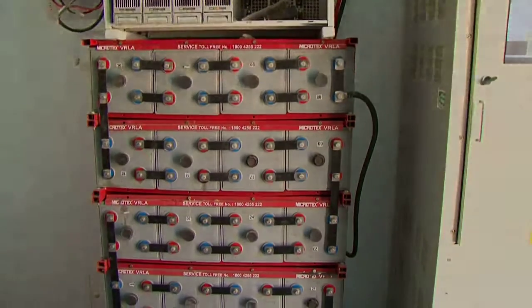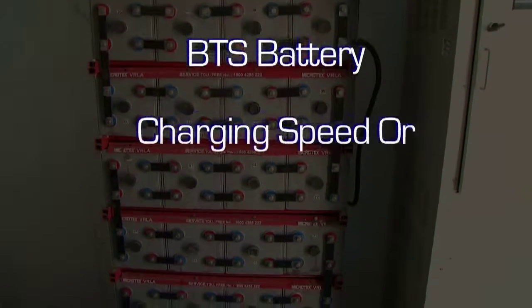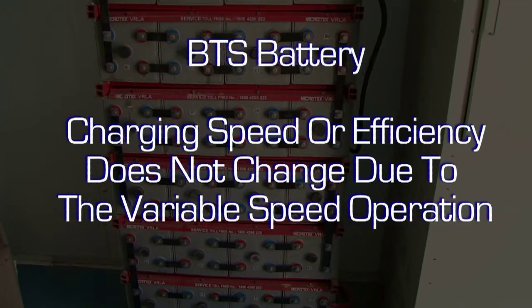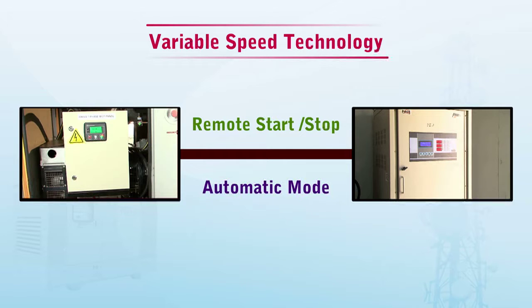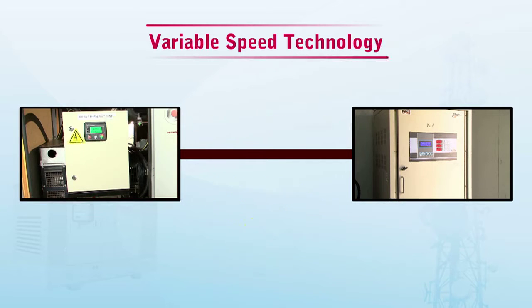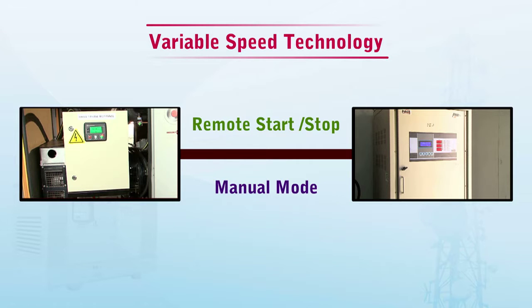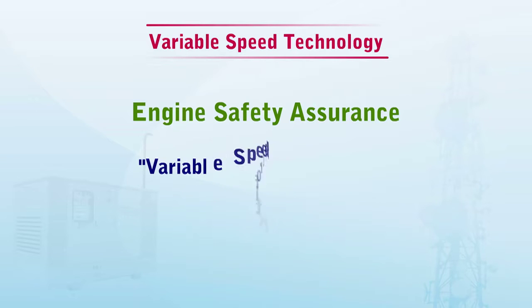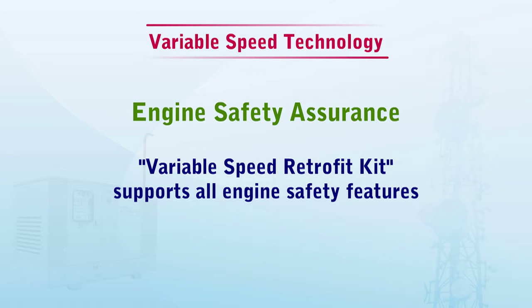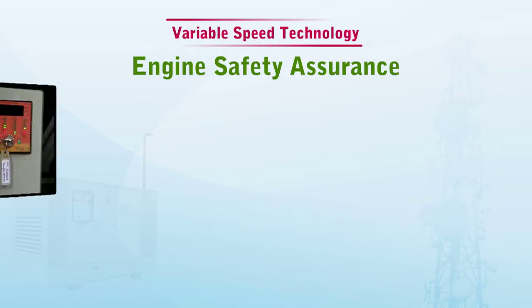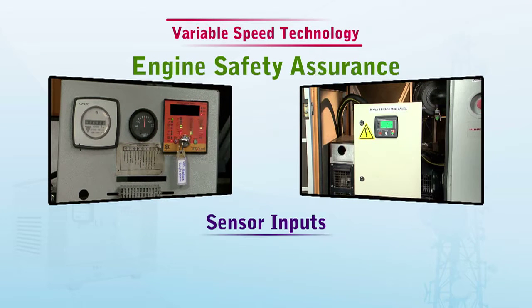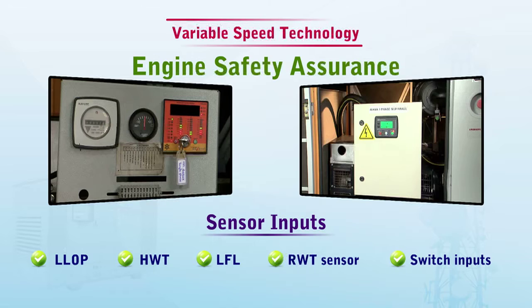One important point to remember is that the BTS battery charging speed and efficiency does not change due to the variable speed operation. The variable speed technology supports remote start-stop as well as fully manual mode. Engine safety assurance. The variable speed retrofit kit supports all engine safety features, and just like the old MCB panel, the new panel also receives LLOP, HWT, LFL, RWT sensor and switch inputs.